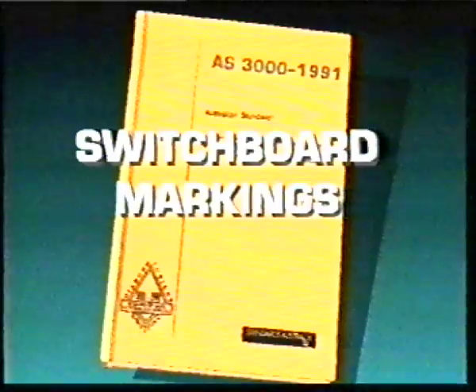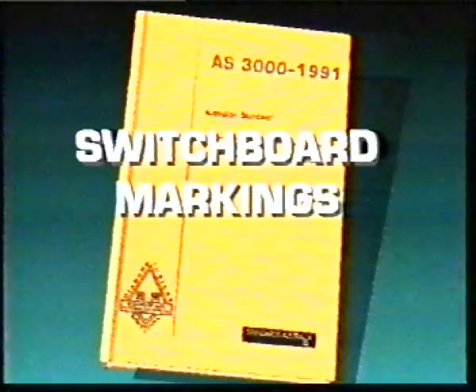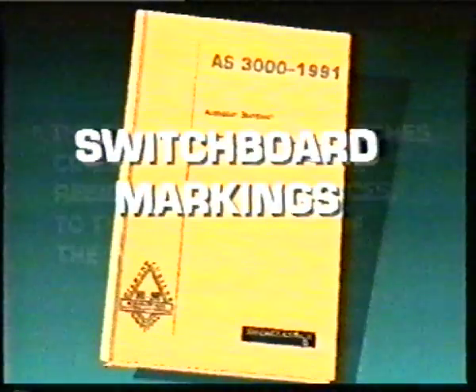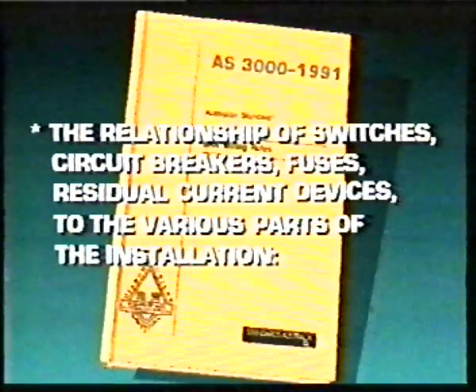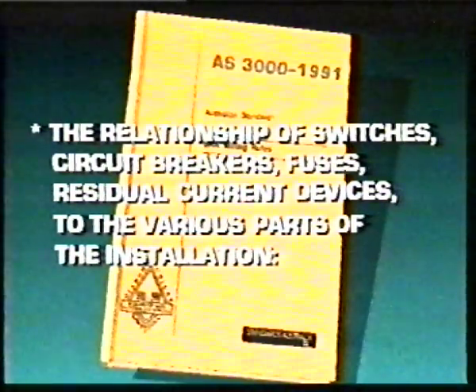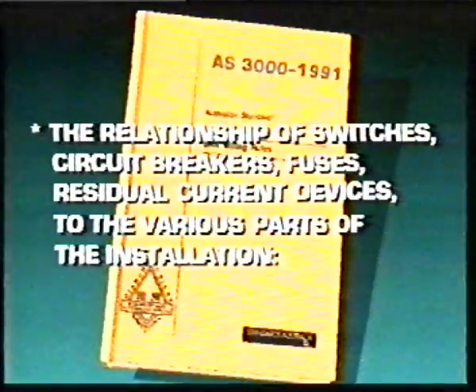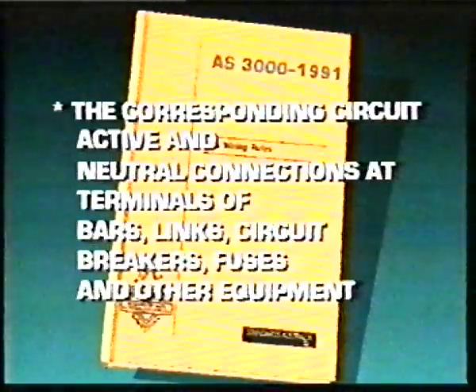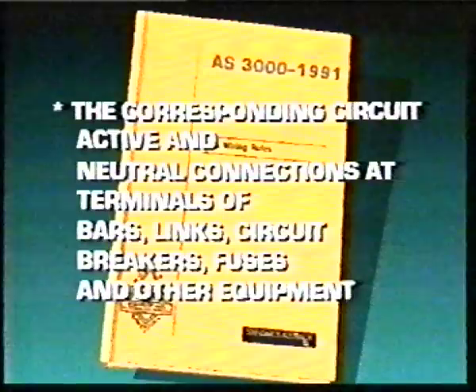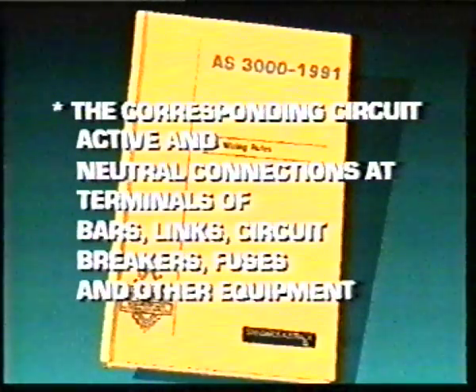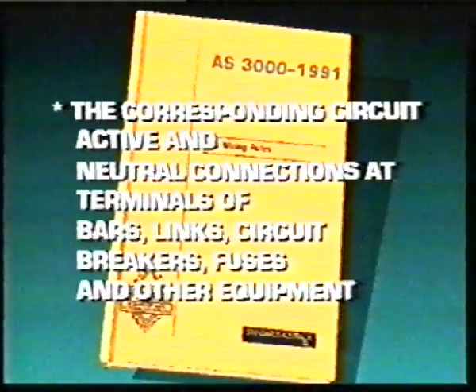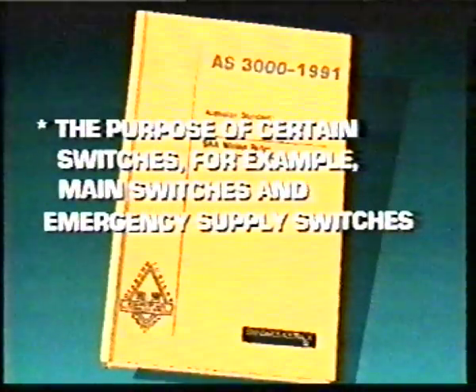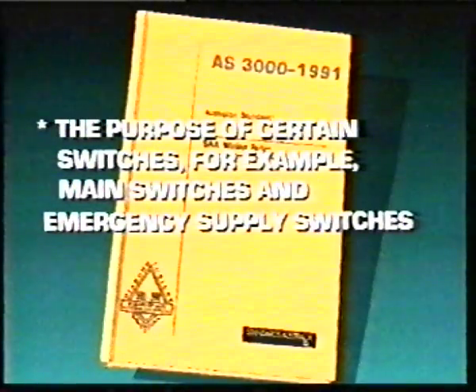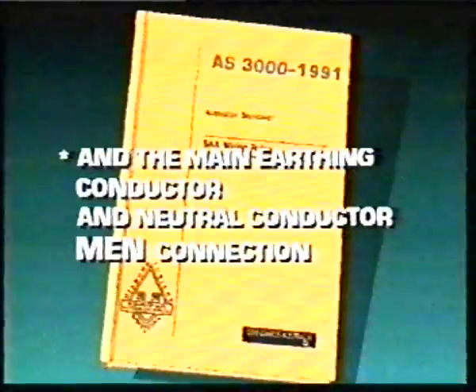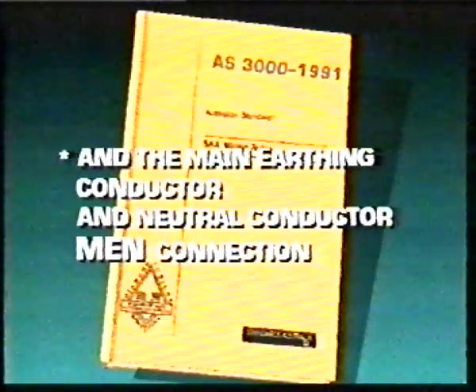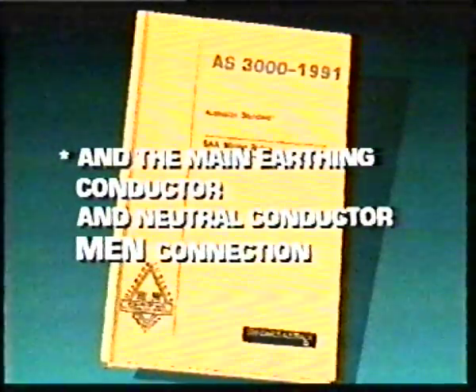There's a requirement within AS3000 that equipment installed on switchboards be marked to identify the relationship of switches, circuit breakers, fuses, residual current devices, etc. to the various parts of the installation, the corresponding circuit active and neutral connections at terminals of bars, links, circuit breakers, fuses and other equipment, the purpose of certain switches, for example main switches and emergency supply switches, and the main earthing conductor and neutral conductor MEN connection.